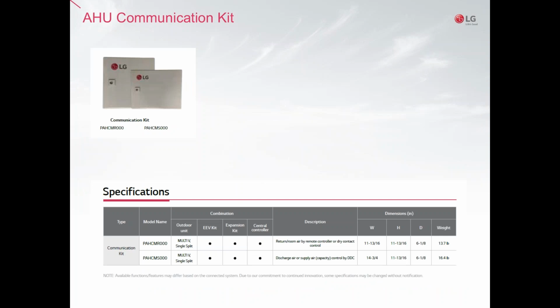Now let's talk about the communication kits. LG Electronics has two types of these. One is called supply air temp control, and the other return air temp control. To select one, the first thing is to decide what the use of the air handling unit is and what type of temperature it will be controlling or will be controlled by. The rule of thumb is that if the air handling unit will be returning most of the air it supplies, and it will be controlled by an ambient temperature sensor, then you will need the return air version, or PAHCMR000. These units are typically controlled by a thermostat in the conditioned area.